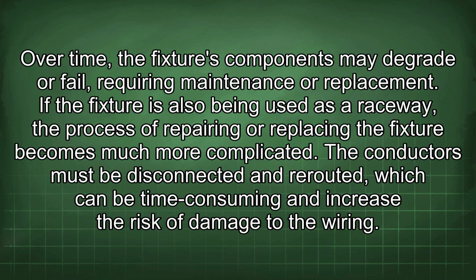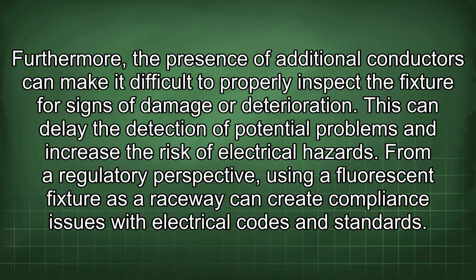Over time, the fixture's components may degrade or fail, requiring maintenance or replacement. If the fixture is also being used as a raceway, the process of repairing or replacing the fixture becomes much more complicated. The conductors must be disconnected and rerouted, which can be time-consuming and increase the risk of damage to the wiring. Furthermore, the presence of additional conductors can make it difficult to properly inspect the fixture for signs of damage or deterioration. This can delay the detection of potential problems and increase the risk of electrical hazards.